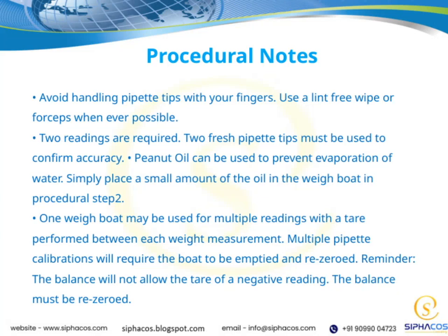Let's discuss some key procedural notes to ensure accuracy during pipetting. First, avoid handling pipette tips with your fingers whenever possible. Instead, use a lint-free wipe or forceps. This helps prevent contamination and maintains tip integrity. Next, when measuring, always perform 2 readings. It's essential to use 2 fresh pipette tips for each measurement to confirm accuracy. Reusing tips can lead to errors.